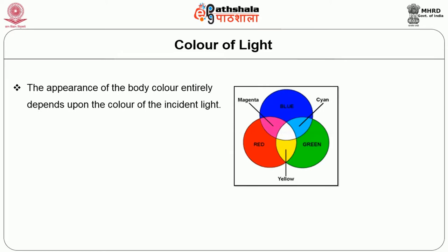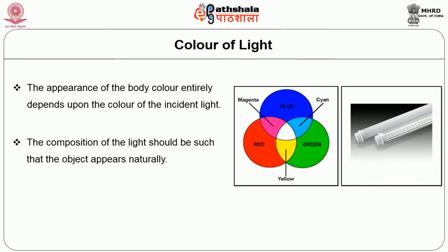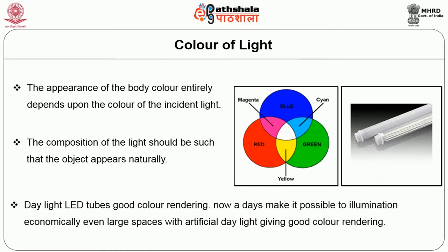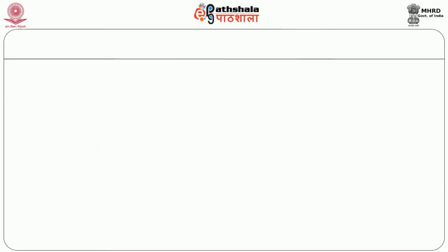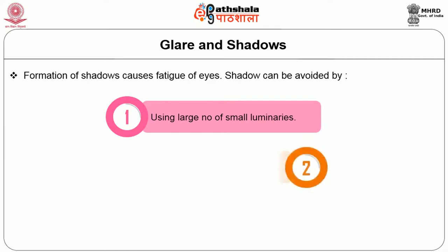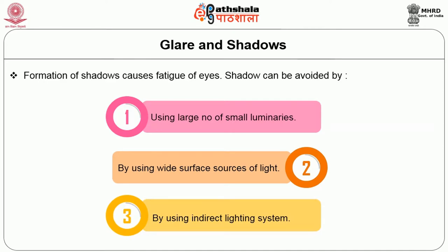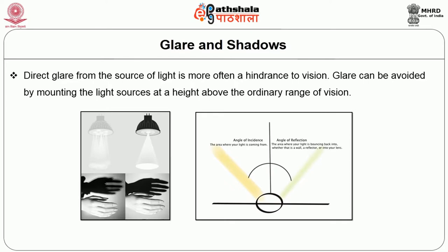Color of light: the appearance of body color entirely depends on the color of the incident light. The composition of the light should be such that objects appear natural. Daylight LED tubes nowadays make it possible to illuminate even large spaces economically with artificial daylight, giving good color rendering. Glare and shadows: formation of shadows causes fatigue for the eyes. Shadows can be avoided by using a large number of small luminaries, wide surface sources of light, or indirect lighting systems. Direct glare from the source of light is more often a hindrance to vision. Glare can be avoided by mounting the light source at a height above the ordinary range of vision.